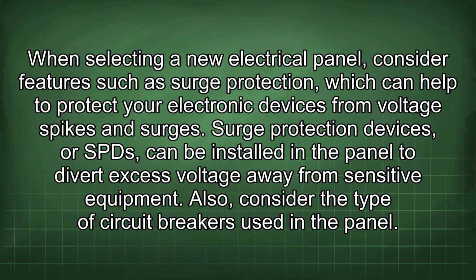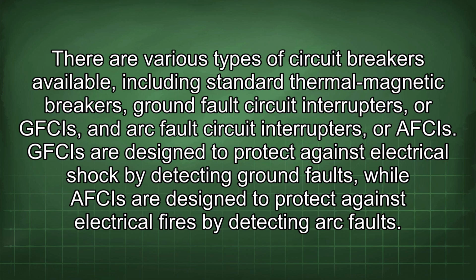When selecting a new electrical panel, consider features such as surge protection, which can help to protect your electronic devices from voltage spikes and surges. Surge protection devices, or SPDs, can be installed in the panel to divert excess voltage away from sensitive equipment. Also, consider the type of circuit breakers used in the panel. There are various types of circuit breakers available, including standard thermomagnetic breakers, ground fault circuit interrupters, or GFCIs, and arc fault circuit interrupters, or AFCIs. GFCIs are designed to protect against electrical shock by detecting ground faults, while AFCIs are designed to protect against electrical fires by detecting arc faults.